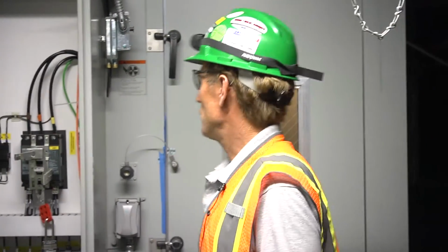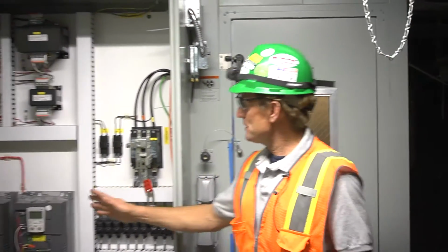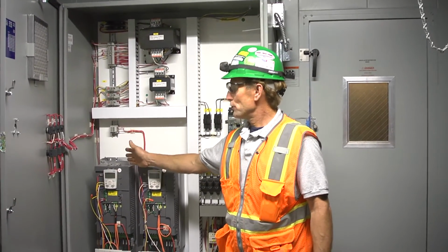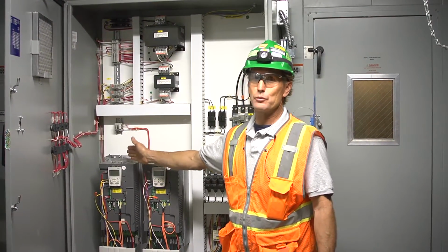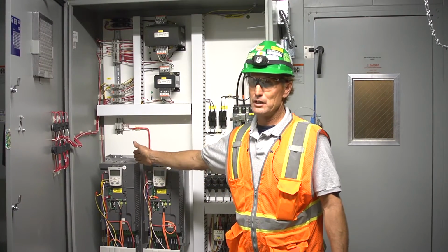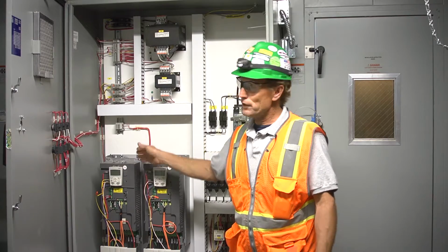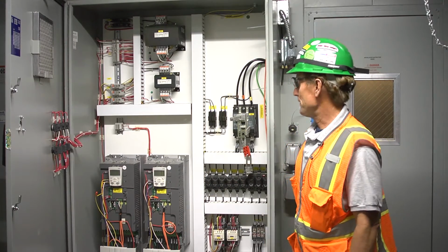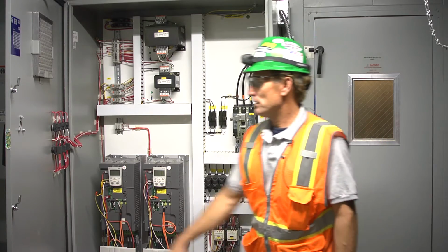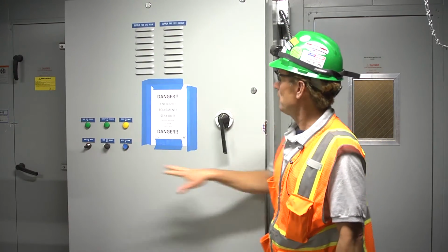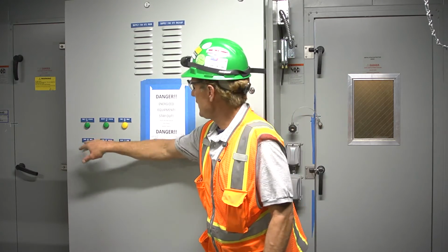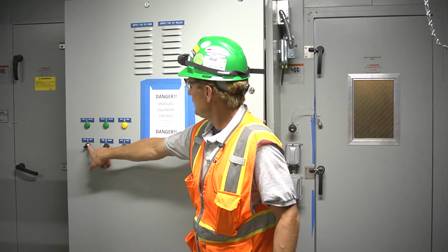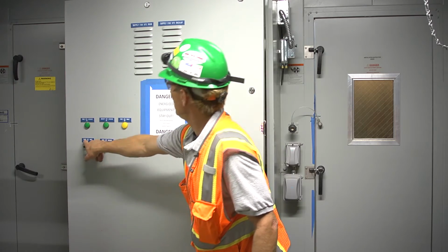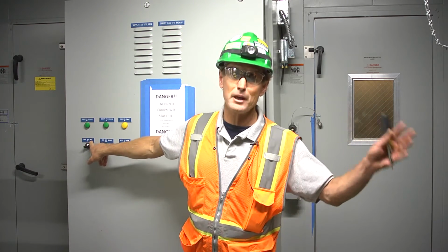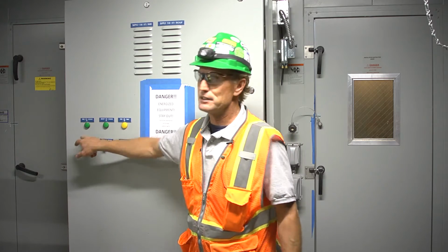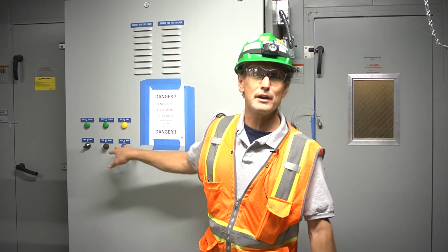Okay? So we have 4 supply fans. All 4 supply fans are provided power through either the main VFD or the backup VFD. So one VFD provides power to 4 fans. So the switching on the 2 VFDs, you have your main VFD switch here. It goes from hand to auto. In auto, it's being run by the building automation system. In hand, it's being run by a local operator right here at the unit.